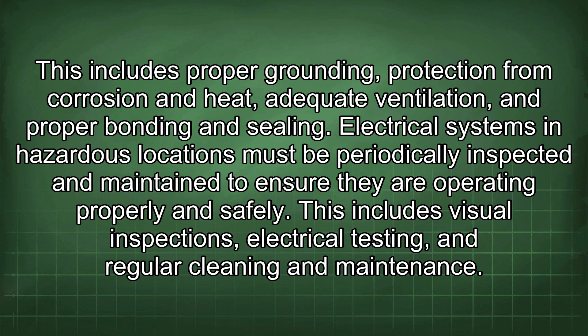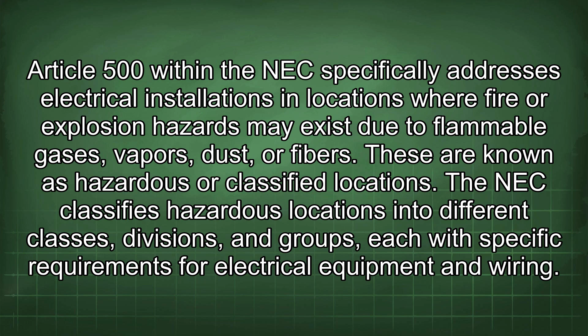The National Electrical Code, or NEC, is a comprehensive set of standards that outline safe electrical practices. Article 500 within the NEC specifically addresses electrical installations in locations where fire or explosion hazards may exist due to flammable gases, vapors, dust, or fibers. These are known as hazardous or classified locations. The NEC classifies hazardous locations into different classes, divisions, and groups, each with specific requirements for electrical equipment and wiring. This classification system helps to ensure that electrical equipment used in these areas does not become a source of ignition.